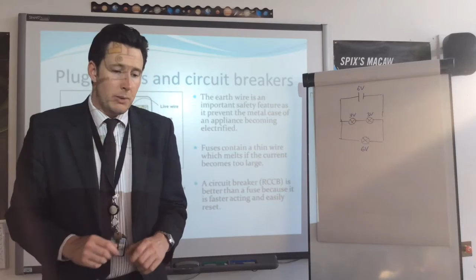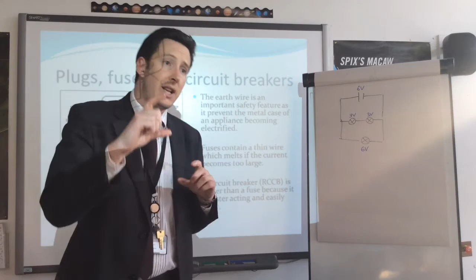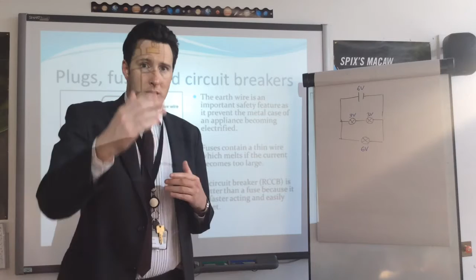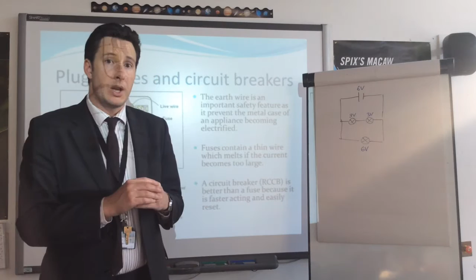So if I had an appliance which had a current of 2.5 amps, I could use a 3 amp fuse because that's bigger than the 2.5. I could technically use the 5 amp fuse as well, but that would not be a good idea because it's much higher than the current that it needs to flow, and in which case would maybe not cut off if the current got too large and there was a risk of danger. So you always attempt to use a fuse that has the current just above the current that you are measuring, but as close to it as you can get.